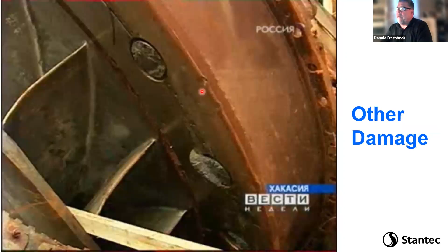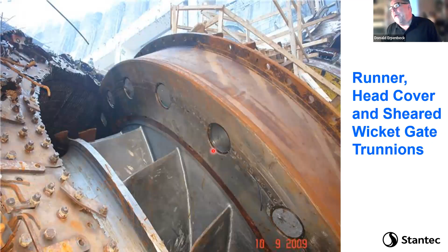Okay, now let's look at some other damage. So this is that head cover piece, and there's a series of things that control the water into the turbine called wicket gates. What you see here is the stems of the wicket gate shafts completely sheared off inside that upper head cover piece. And you might not know what that is, but if I pull back a little bit, you'll see here all the wicket gate stems completely sheared off. So it's pretty clear it failed in a torsional failure on the wicket gates. And those are probably about 25 or 30 centimeters in diameter. They're not as small as they look here.